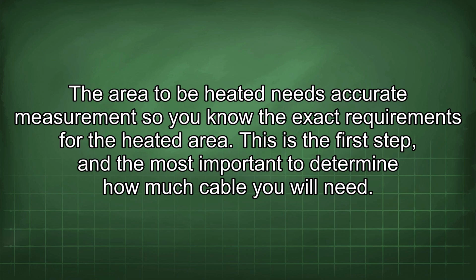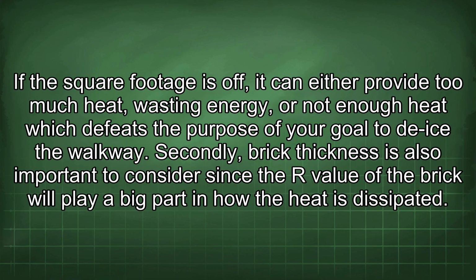The area to be heated needs accurate measurement so you know the exact requirements for the heated area. This is the first step and the most important to determine how much cable you will need. If the square footage is off, it can either provide too much heat, wasting energy, or not enough heat, which defeats the purpose of your goal to de-ice the walkway.